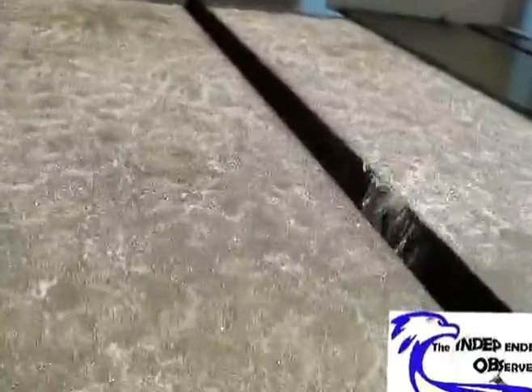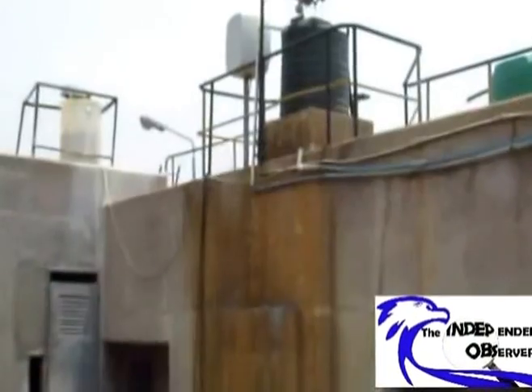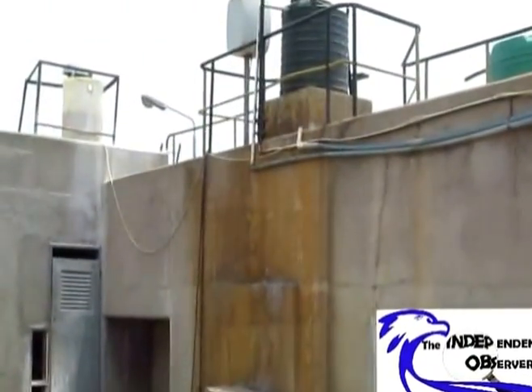That is what we call plain sedimentation. Then after that, the water goes to the next component, which is the premixer or the repartition box. Now at the repartition box, it is at that juncture where there are two green tanks, as you can see. One of the tanks is the one we use for dosing aluminum sulfate solution. Then the other one is meant to dose lime. So in other words, at the premixer or the repartition box, that's where we start adding in water treatment chemicals.